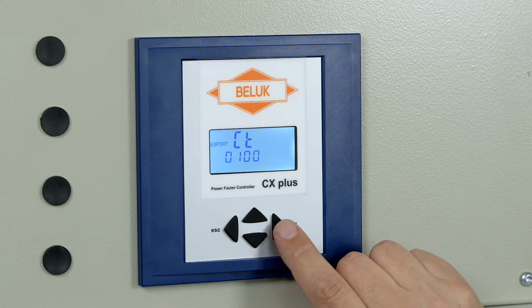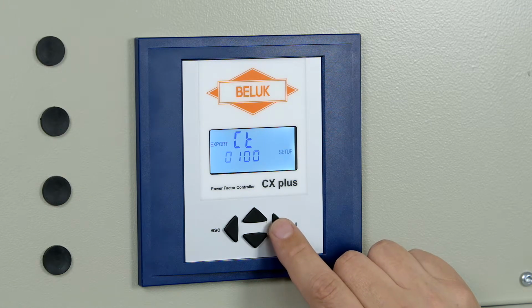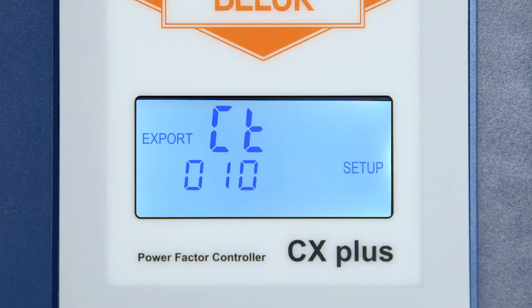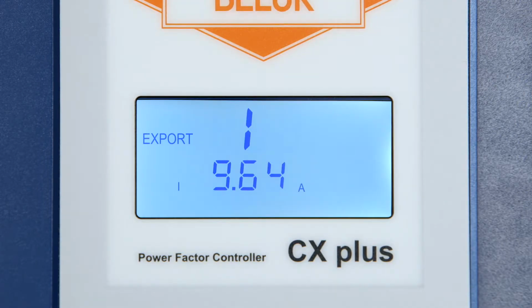Then the current transformer factor CT must be entered. For a 500-to-5 converter, this would be 100. Again, the value is displayed for 1 second. The current measurement value appears on the display for 3 seconds for checking purposes.